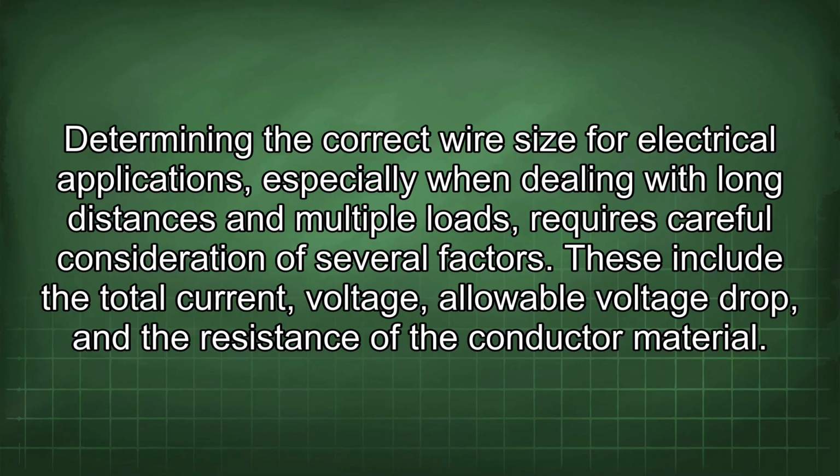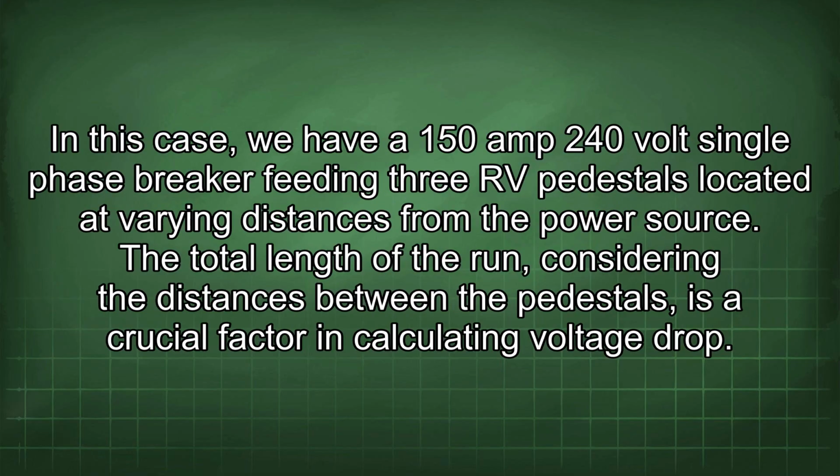Determining the correct wire size for electrical applications, especially when dealing with long distances and multiple loads, requires careful consideration of several factors. These include the total current, voltage, allowable voltage drop, and the resistance of the conductor material. In this case, we have a 150 amp 240 volt single-phase breaker feeding 3 RV pedestals located at varying distances from the power source.